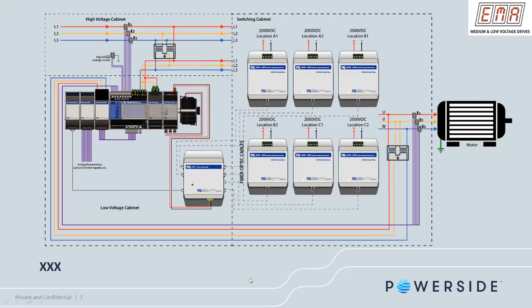Okay, so like I was saying earlier, the drive scan can do gapless monitoring of the health of the VFD, including bus capacitors. We can look at the input power monitoring, which is your input voltage, input current, and input harmonics. We can also look at the output power monitoring, which is your output voltage and output current. We can look at the internal power supplies of the VFD on the low voltage section, which is your 15 volts, minus 15 volts, 24 volts, and 5 volts power supply. We can check the temperature of the cabinet, determine the humidity of the cabinet, determine the pressure inside the cabinet, and we can also determine vibration on these enclosures inside the drive cabinet.